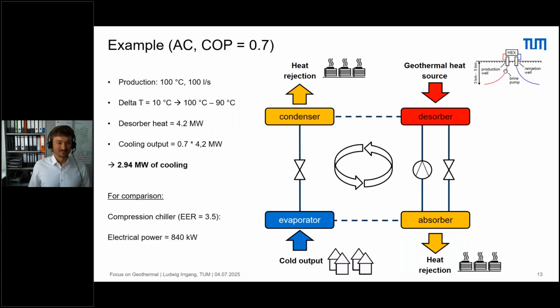To give you a more practical understanding, if we would have, for example, 100 liters per second at 100 degrees and use just 10 degrees of the brine temperature for the absorption chiller, we can already produce a cooling output of almost 3 megawatts. And if you look at the classical compression chiller with an EER of 3.5, we would use 840 kilowatts for the same cooling output. So there you can see that a lot of geothermal projects have the potential to produce high amounts of cold and thereby save a lot of electrical energy. As you can see, we have the heat rejection at condenser and absorber. That's what I mentioned earlier, that in comparison to a classical compression chiller, we have additional heat output, and that should always be considered when installing an absorption chiller.